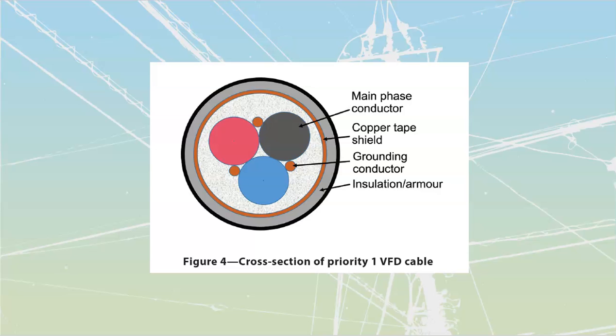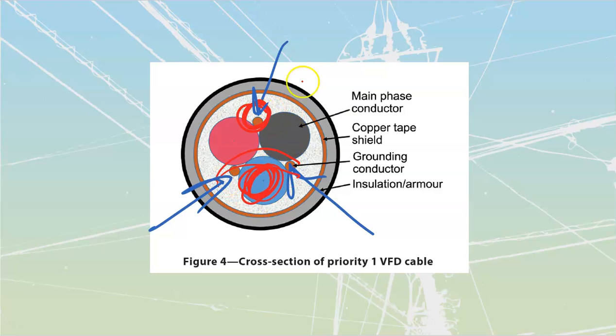We also found that symmetrical arrangement was going to be necessary, where I take my grounding, or bonding conductor, and split it into 3 components, running them across so each one gets the exact same amount of frequency. When I only had a single bond conductor sitting over here, anything the C phase had for flux was effectively blocked by the other 2 conductors, because they have their own fields at any given time as well.